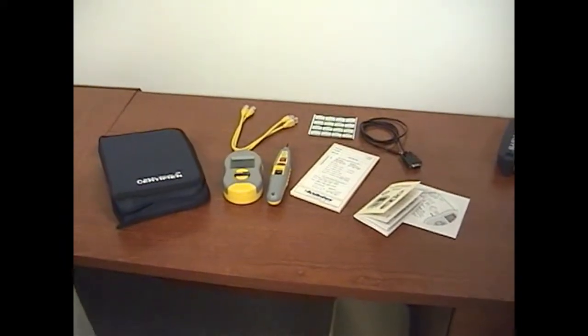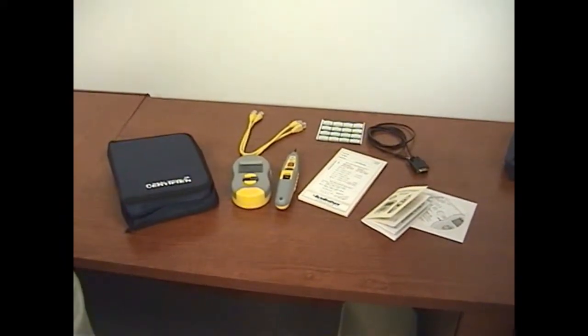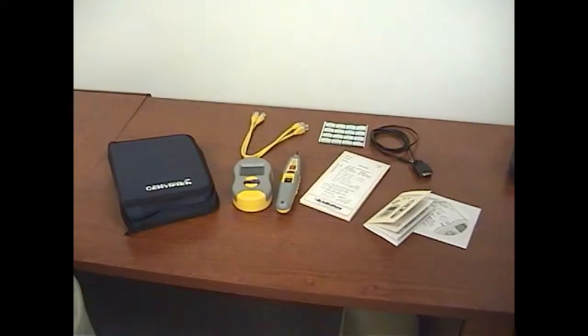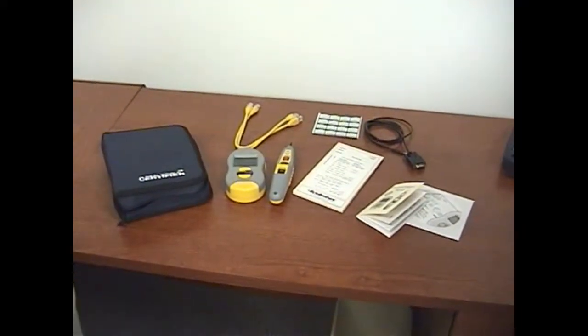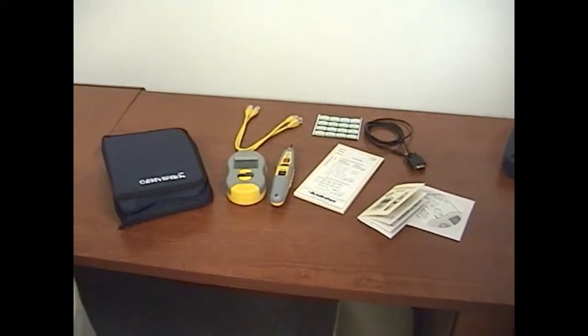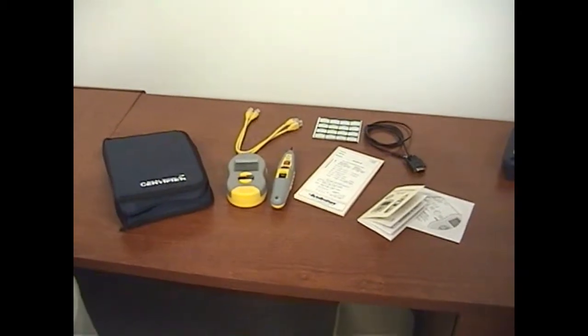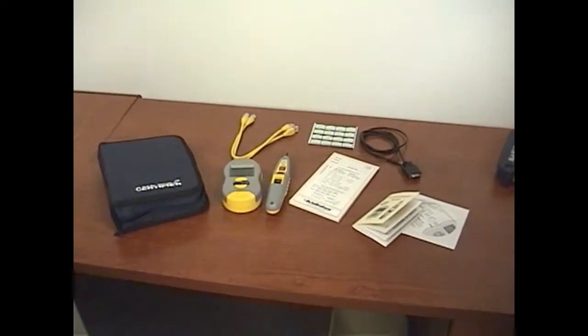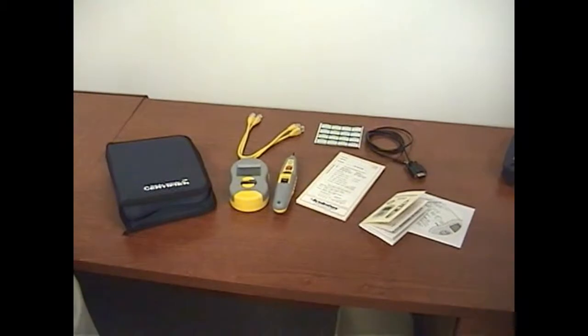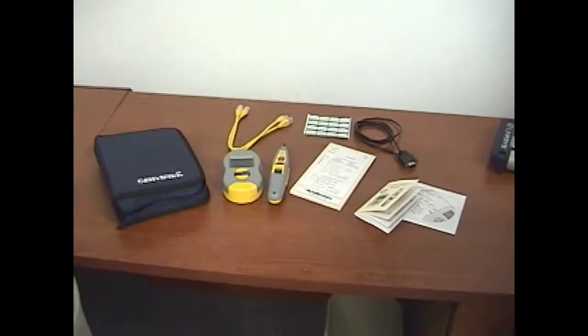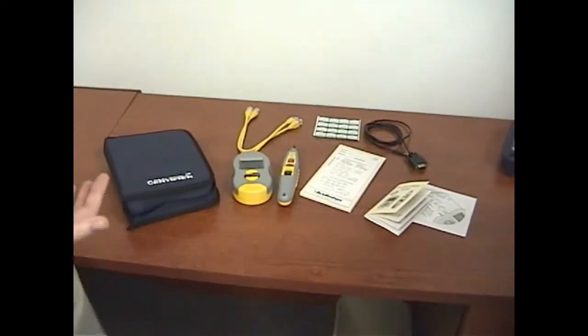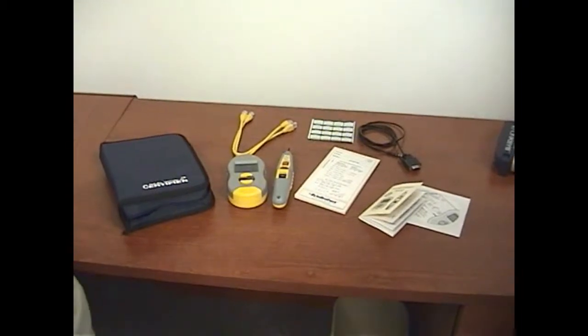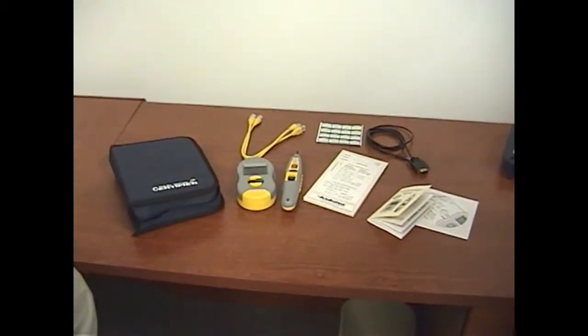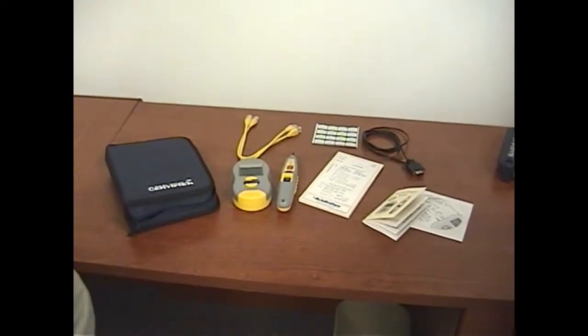People say, what is the real-world certifier? Well, it's a tester that does all of the most common tests you'd expect it to perform on cables, like giving you an accurate cable length, telling you whether the cable has an open, a short, a split pair, and if so, how many feet down the cable that split pair or open is. In other words, you get some good troubleshooting tools.